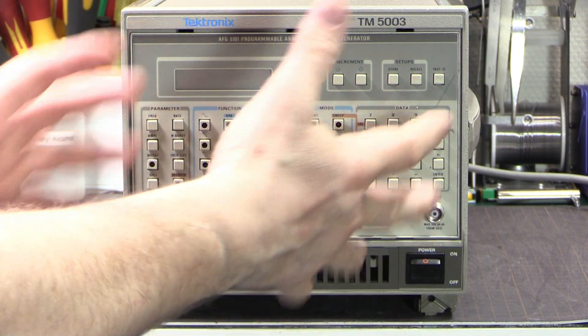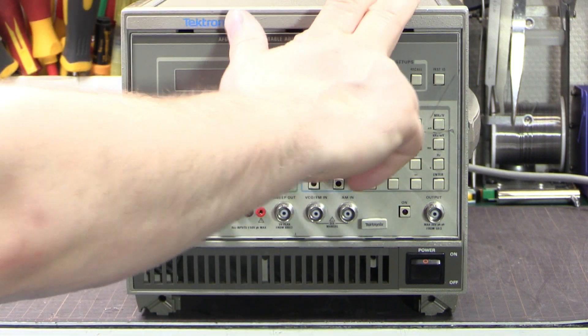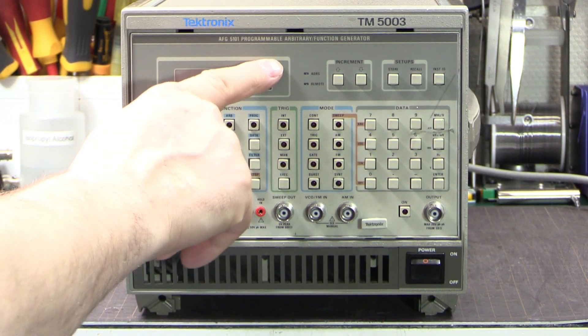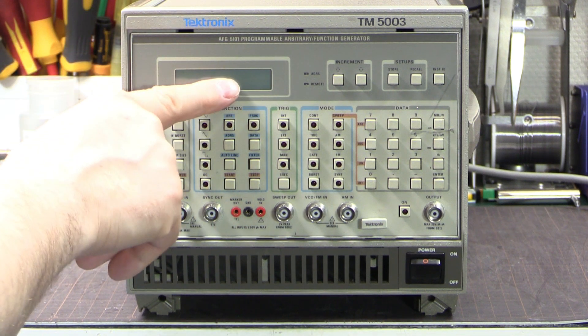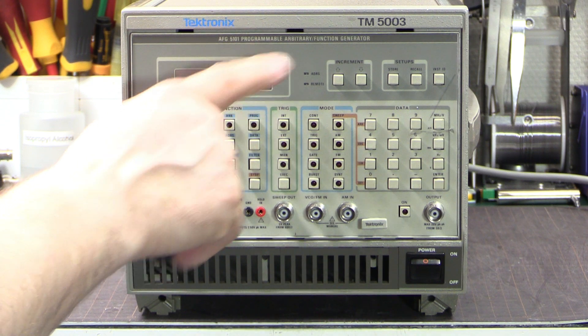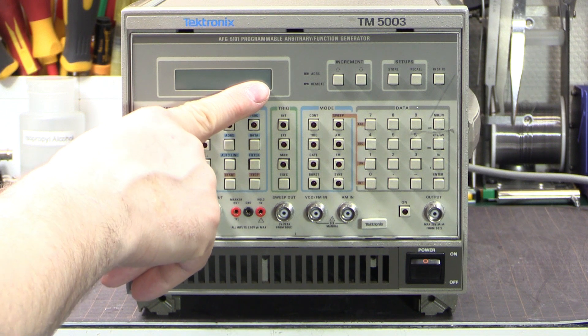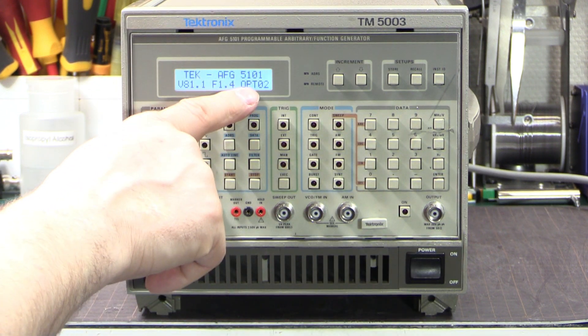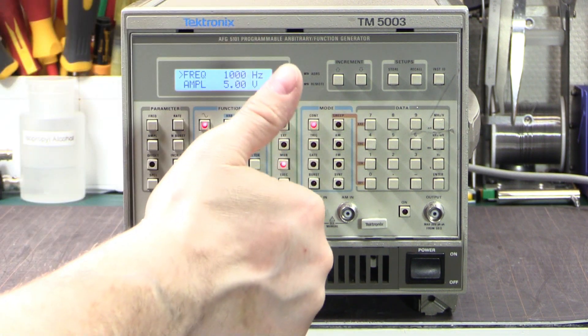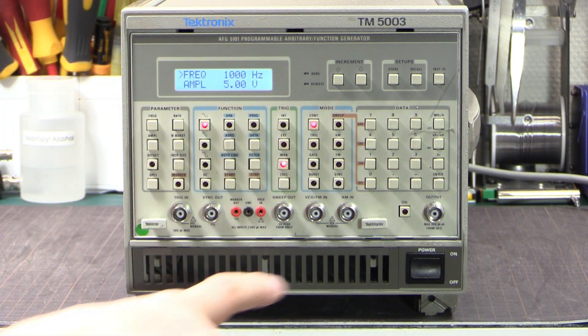All right I've got the option board installed and we're ready to test. So to install the option board into the unit it's really easy. Take the back panel off, slide it in, click into place, put the back panel on and you're done. So that's been done. We've got the module sitting in the TM5003 mainframe and we're ready to turn on and see what happens. So when I do turn it on it'll say AFG5101 blah blah blah on the top line. At the bottom line at the left it'll give us some firmware information and then on the right at the bottom it should say OPT02 to let us know that the option two is being detected.